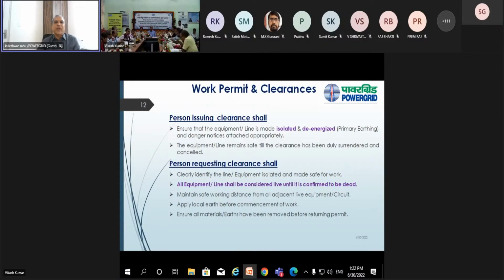Then work permit and clearances. The important thing: the person who is issuing the clearance ensures that the equipment line is isolated and de-energized through the primary earthing and danger notice attached appropriately. The equipment lines remain safe till the clearance has been duly surrendered and cancelled. So this is the responsibility of who is issuing the permit and who is requesting and working. Clearly identify the line, equipment, and isolation for making the work safe.